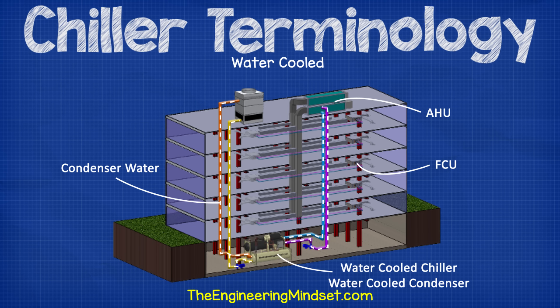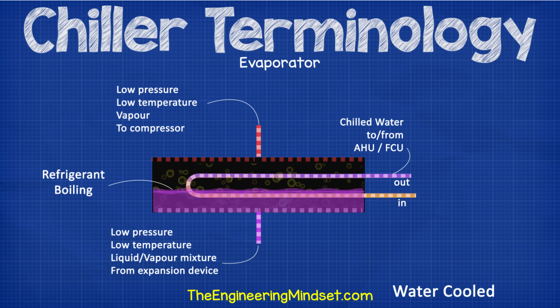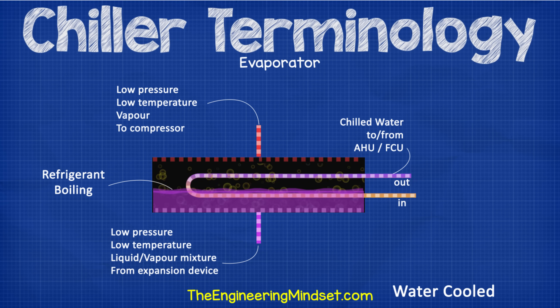Water-cooled. This refers to a type of chiller which uses the condenser water and cooling towers to remove the heat from the condenser. These are located inside the building, typically in the basement. Evaporator. The evaporator is where the unwanted heat of the building is collected before being transferred over to the condenser. As the unwanted heat enters the evaporator, it will cause the refrigerant to boil and evaporate inside. As it evaporates, it will carry the heat away over to the condenser. The refrigerant enters the evaporator as a low-pressure liquid, and as it evaporates, it will leave as a low-pressure vapor.